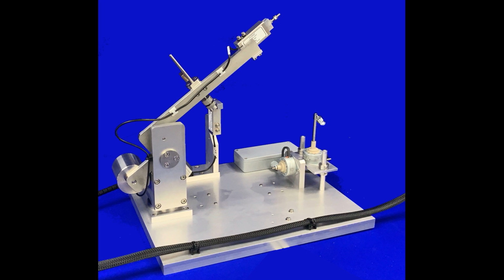The T79 comprises a base plate with load and friction force measuring systems. The fixed pin or ball sample is carried on a trunnion and gimbal mounted beam. This is counterbalanced to give a neutral balance and to bring the centre of gravity into the same plane as the contact. Load is applied by a linear stepper motor and spring with a force transducer for load measurement.